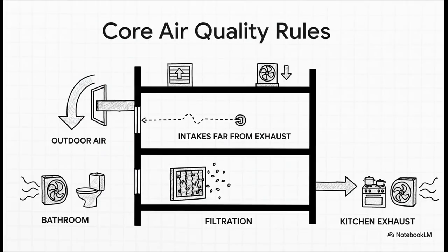So, let's just recap these core air quality rules. Every space has a mandatory minimum for outdoor air. You can't guess. Your fresh air intakes have to be far away from any exhaust outlets, at least 3 meters. Your filters have a minimum rating. MERV 8 is the baseline. And places like bathrooms and kitchens have specific, non-negotiable exhaust rates. Get these right, and you're already way ahead of the game.